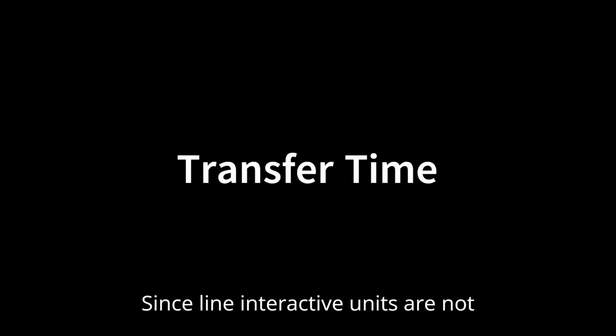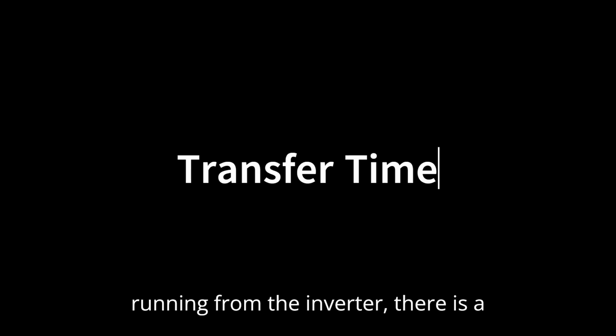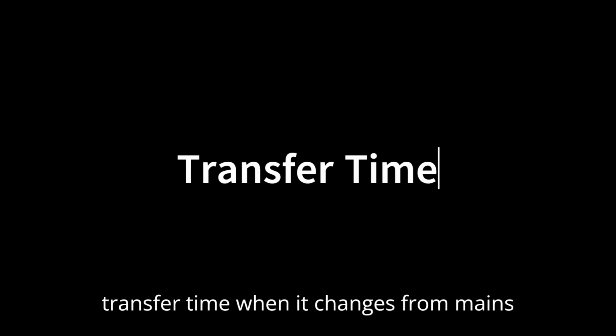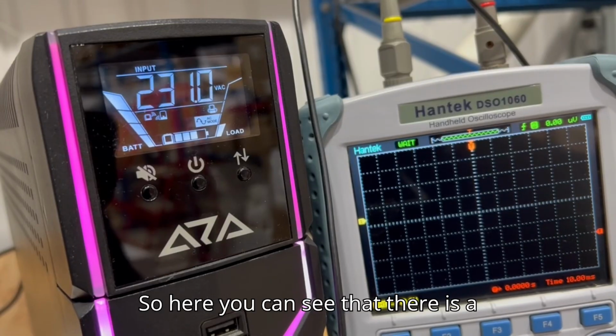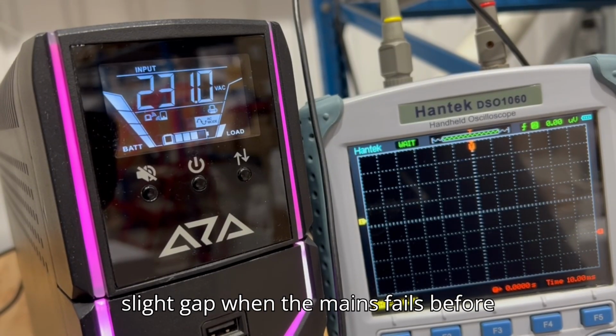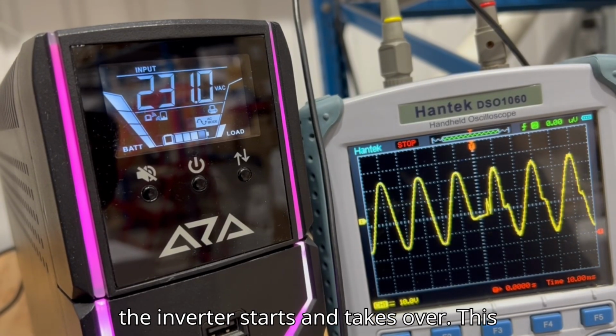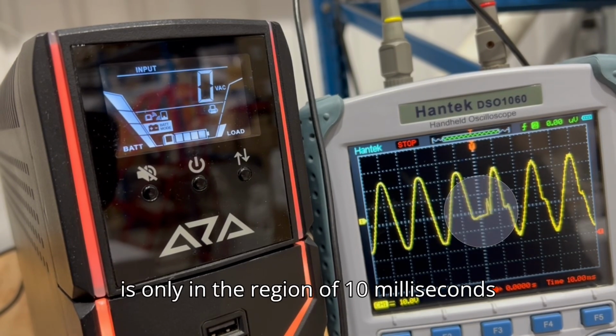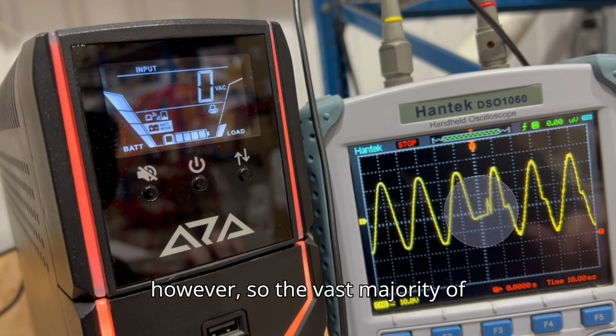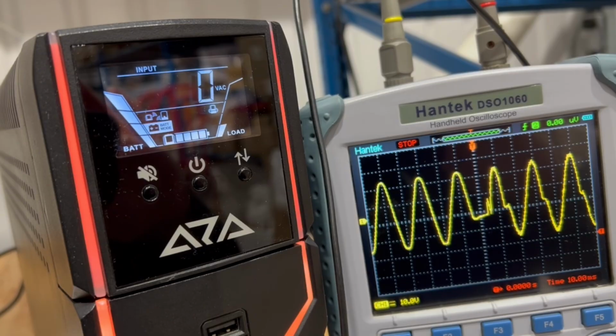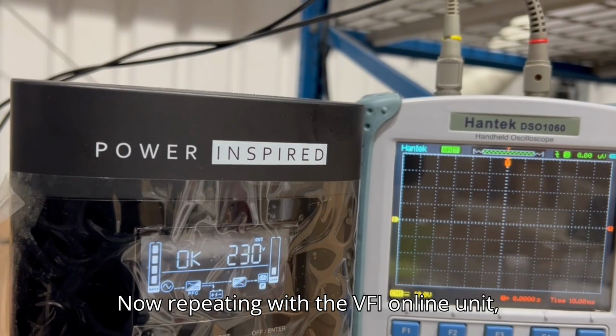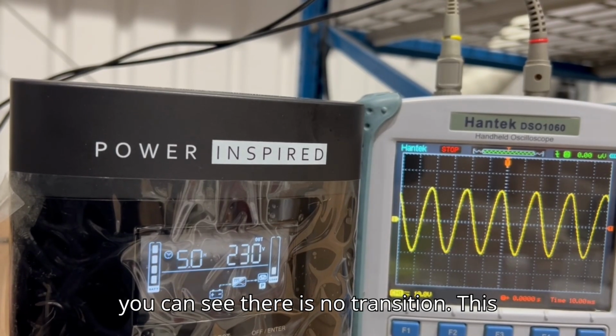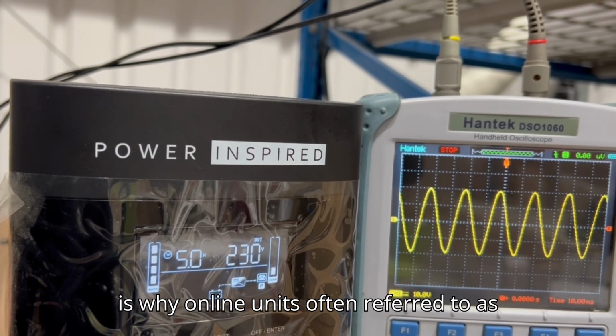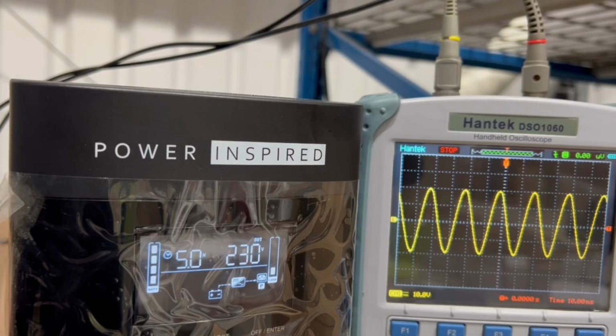Since line interactive units are not running from the inverter, there is a transfer time when it changes from mains to battery. So here you can see that there is a slight gap when the mains fails before the inverter starts and takes over. This is only in the region of 10 milliseconds however, so the vast majority of equipment will not notice this. Now repeating with the VFI online unit, you can see there is no transition. This is why online units are often referred to as no-break UPS.